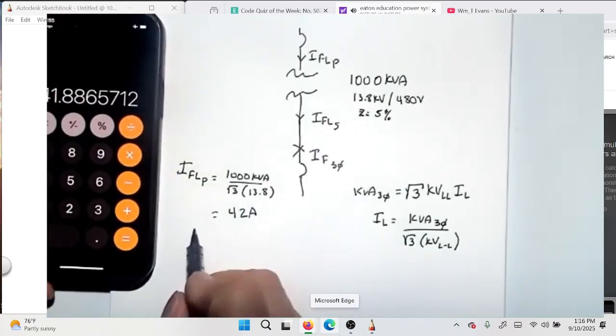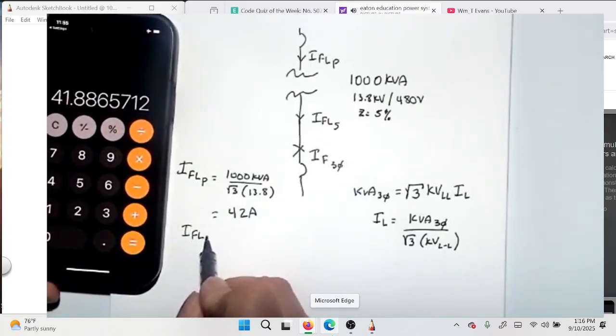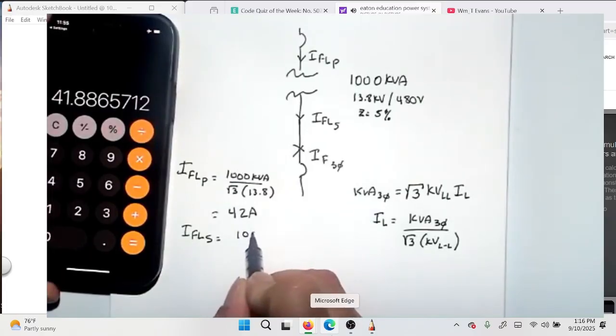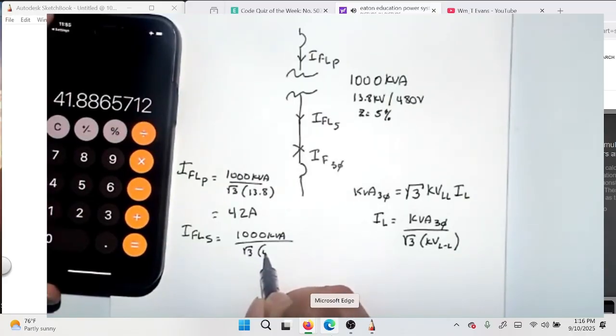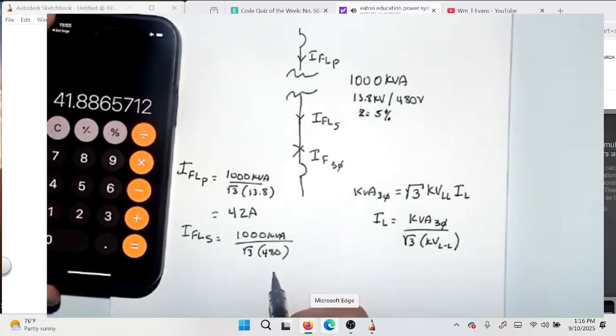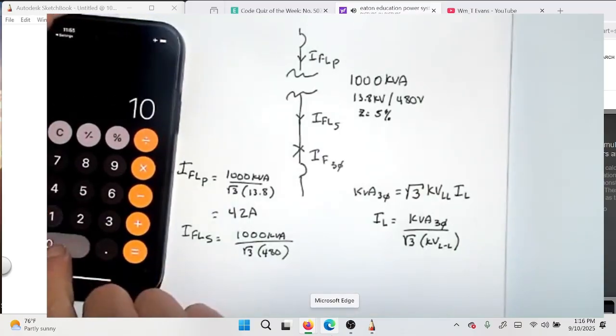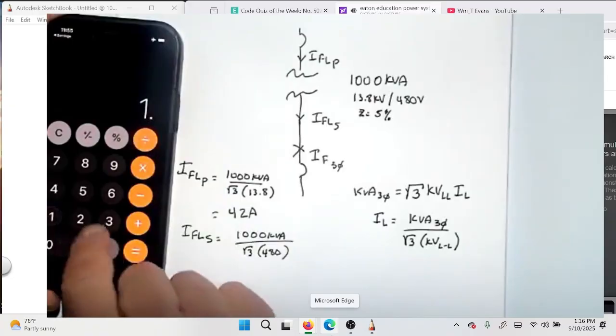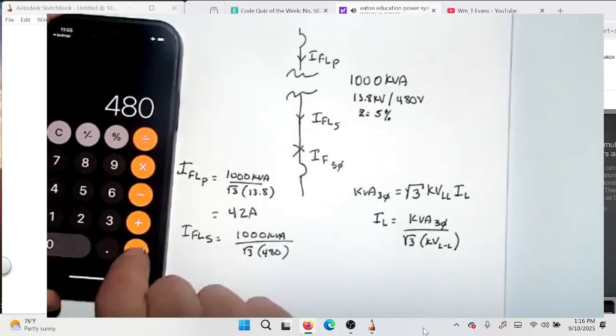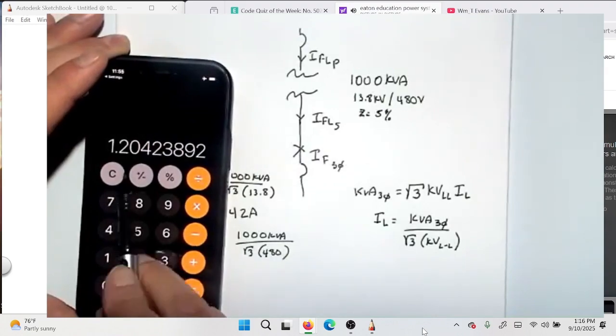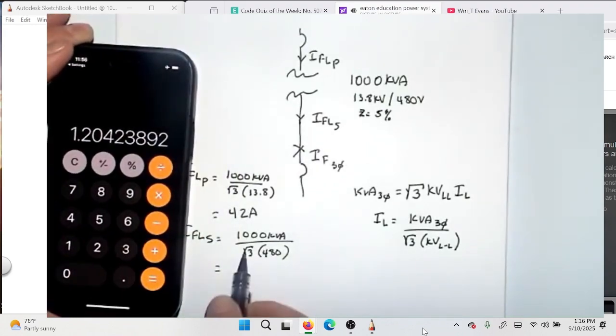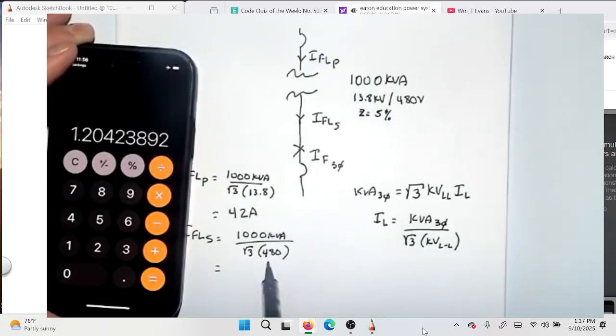Okay. Now, if we want to look at the secondary current, I full load secondary, we would take 1000 kVA divided by the square root of 3 divided by 480, right? Well, here's what's going to get you in trouble. If you do that, 1000 divided by 1.73 divided by 480, your current is 1.2 amps. And if you have 1.2 amps on the secondary and 42 amps on the primary, you should know that something's wrong. And in fact, what you forgot is this is kV line to line on the bottom. So we have to do 0.48.